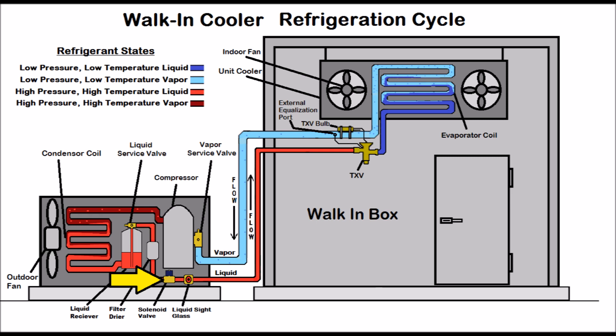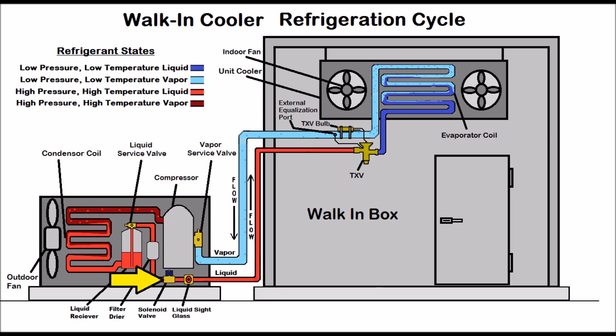The system you're working on may or may not have a solenoid valve. If it doesn't have a solenoid valve and doesn't have a pressure control, the system is simply turned on and off by a mechanical or electronic thermostat. In this example we're showing a liquid solenoid valve used as a pump-down feature on a system with a low pressure control. The sub-cooled liquid refrigerant heads through the liquid solenoid valve.